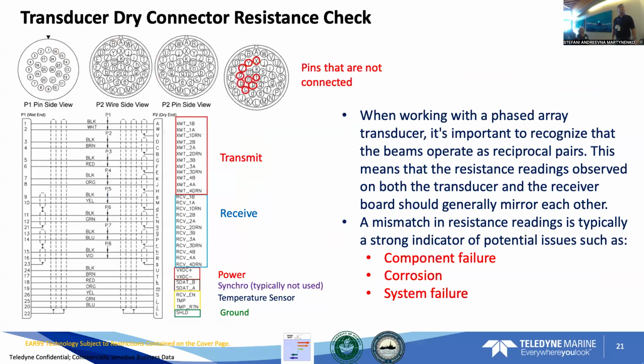So that leads to the transducer dry resistance check. This is the actual wiring diagram. This is what the wet end to the transducer portion looks like, and this will be the dry side. I made this little cheat sheet for whenever I'm terminating these. These pins right here are actually not connected to anything. They're not used, so it's just good to know.